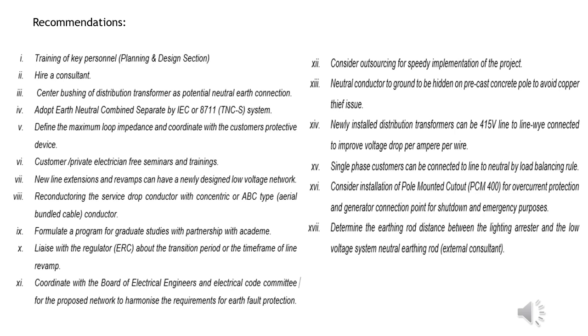So finally, the recommendations are: training of key personnel from the planning and design section; hire a consultant for this specific problem; utilize the center bushing of the distribution transformer as a potential neutral earth connection; adopt the TN-C-S system of IEC or 8711; define the maximum loop impedance and coordinate with the customer's protective device; and conduct free seminars and trainings for private electricians and customers.